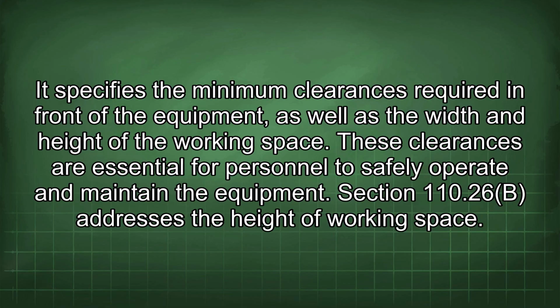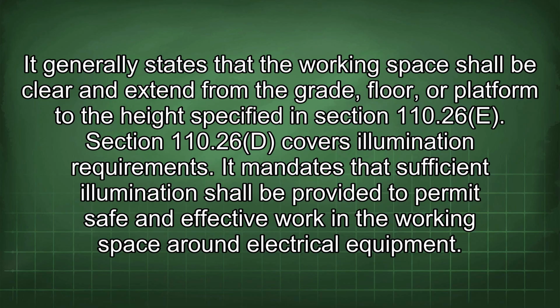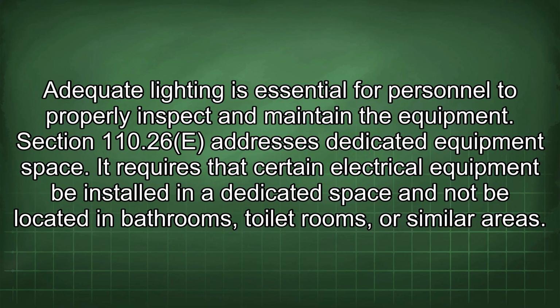Section 110.26b addresses the height of working space. It generally states that the working space shall be clear and extend from the grade, floor, or platform to the height specified in Section 110.26e. Section 110.26d covers illumination requirements. It mandates that sufficient illumination shall be provided to permit safe and effective work in the working space around electrical equipment. Adequate lighting is essential for personnel to properly inspect and maintain the equipment.